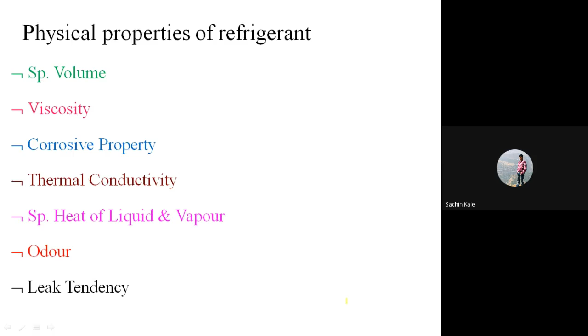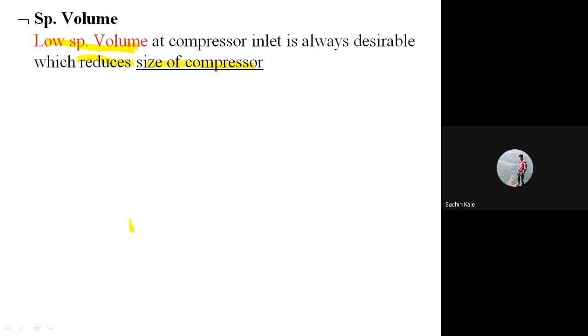Out of that, specific volume: how is it affecting the refrigeration system? The specific volume of a refrigerant affects the compressor, because depending upon the specific volume of the refrigerant, we select the compressor, and the work consumed by the compressor also depends on it. So while selecting the refrigerant, we have to select one which has low specific volume, because with low specific volume the size of the compressor will be smaller and the work consumed by the compressor will keep reducing.